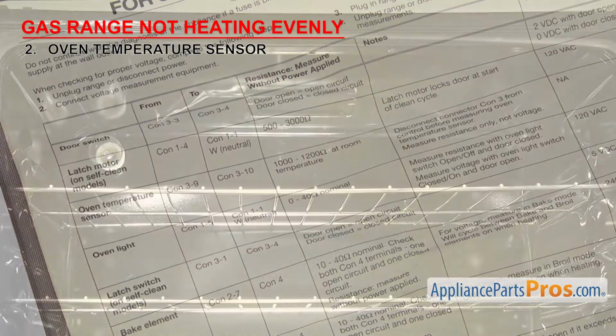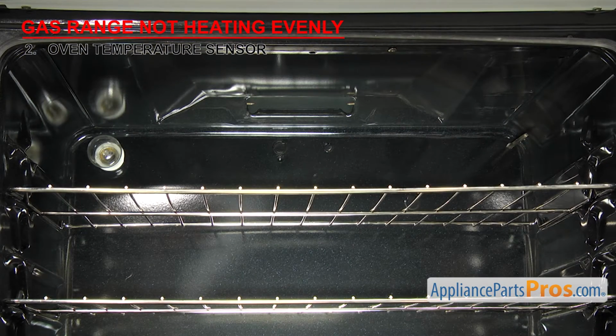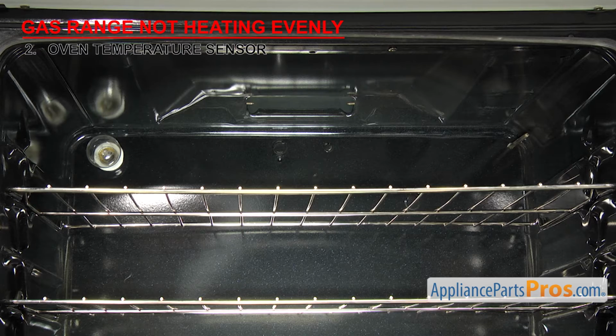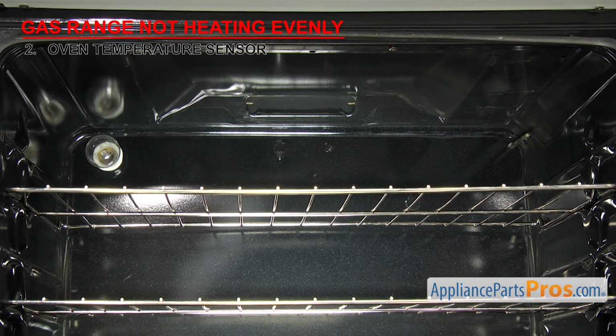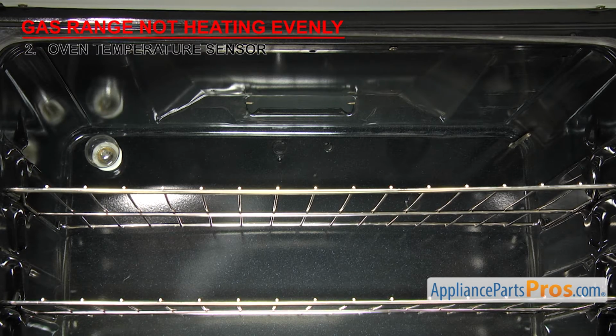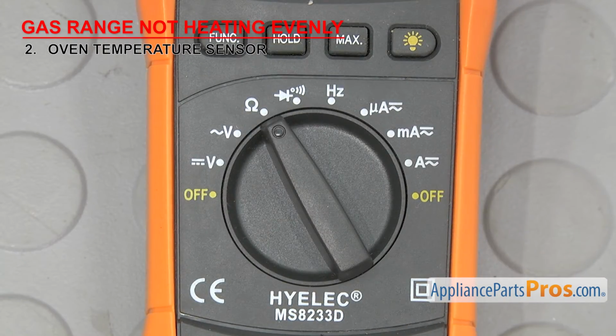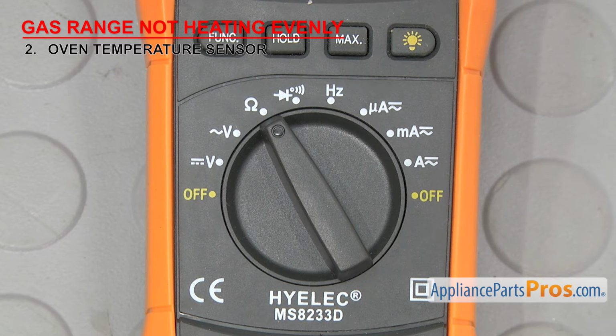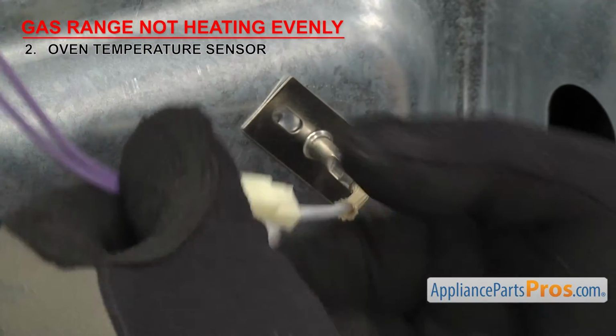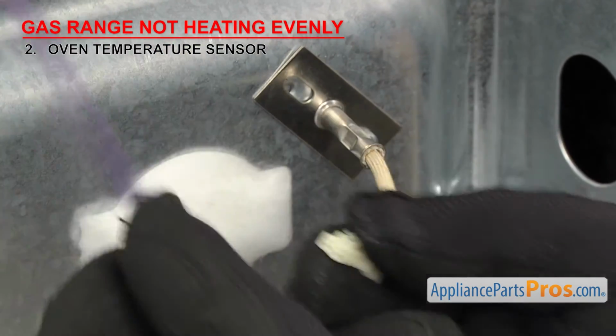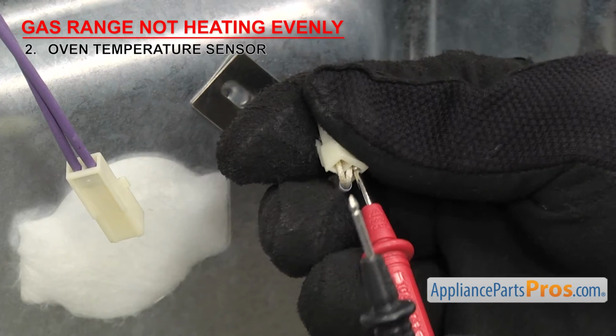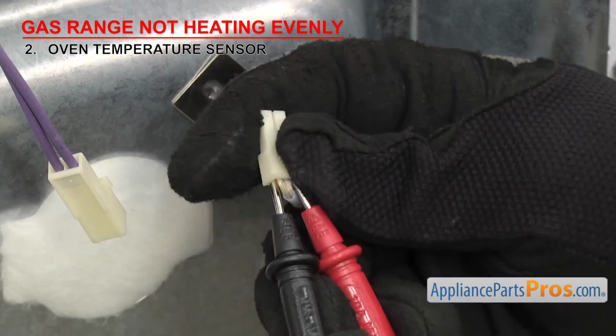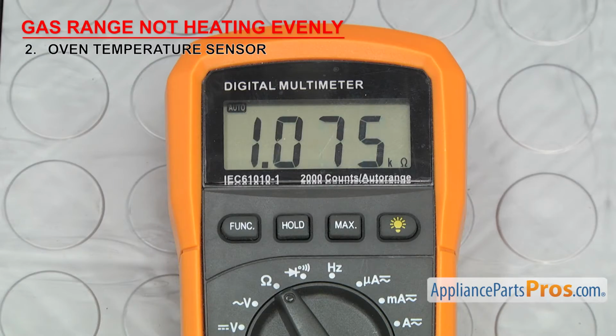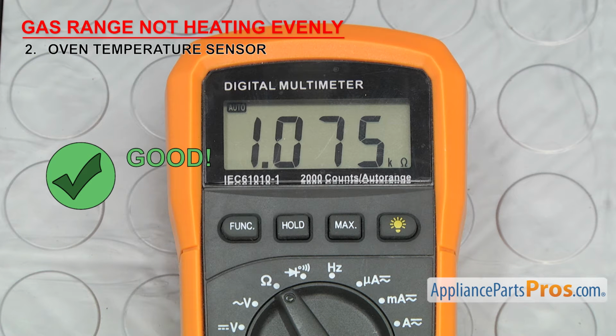The sensor can fail in 2 ways. If the ohms reading is off, it could cause the oven temperature to be different than what you selected. Or if it's totally failed and you don't get a reading at all, then the range won't start. So set your meter to ohms. Our meter automatically detects whatever ohms are coming in, but you may need to set your meter to read the proper ohm level. Once you have access to the sensor, remove the wires and touch a test probe to each terminal. If the ohms reading is way off or you don't get a reading at all, it'll have to be replaced.